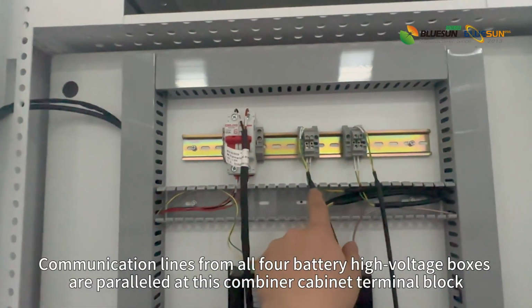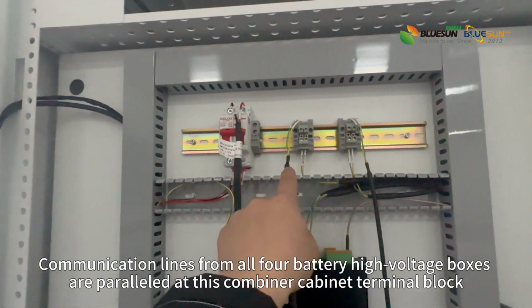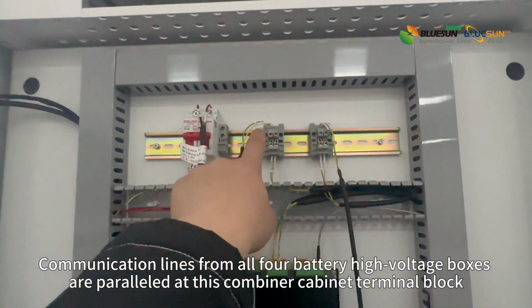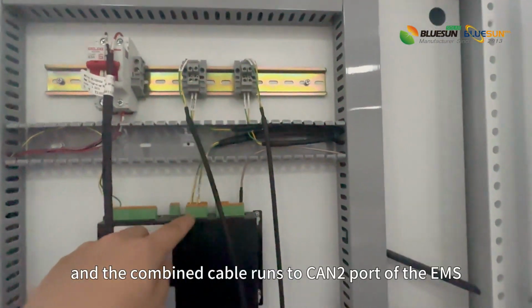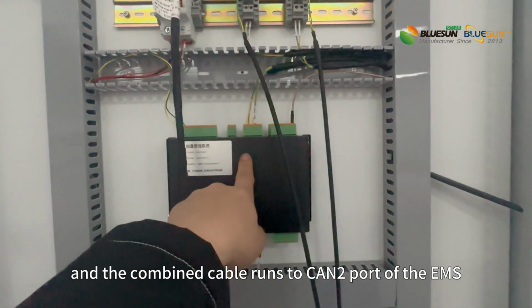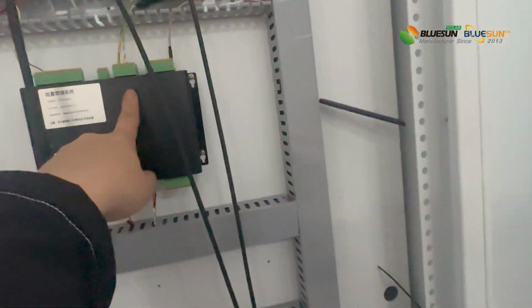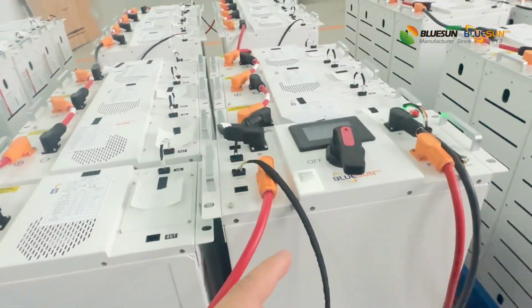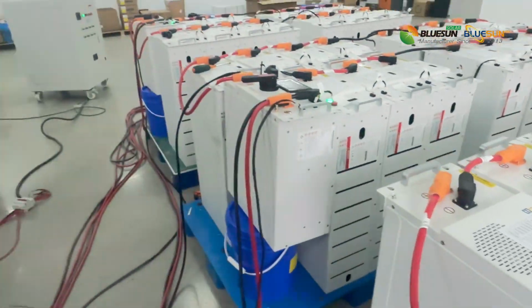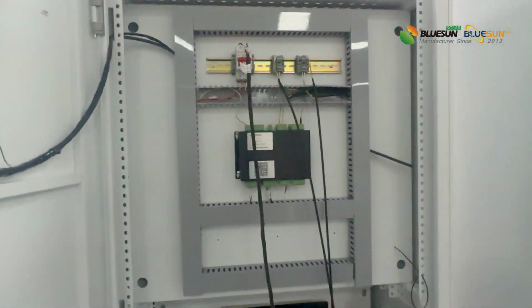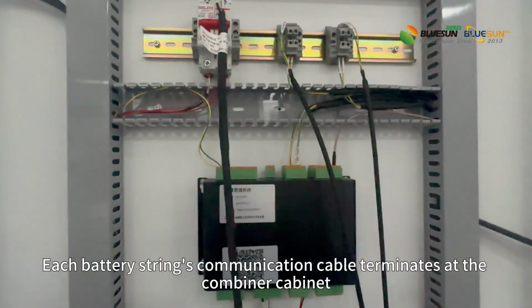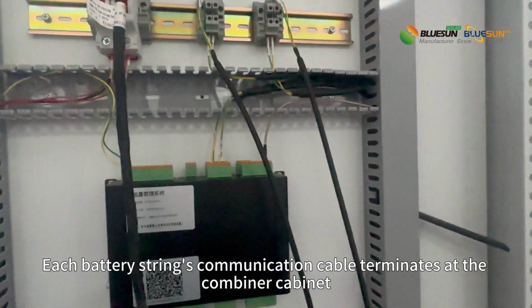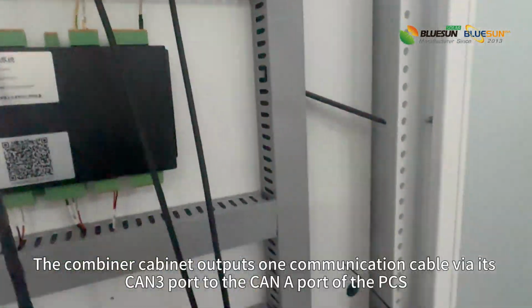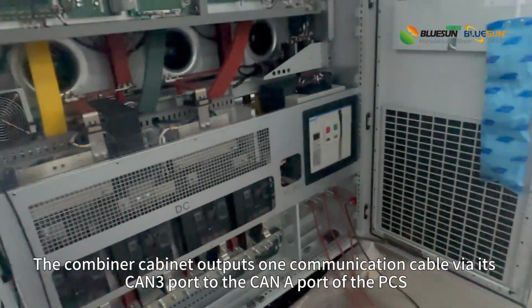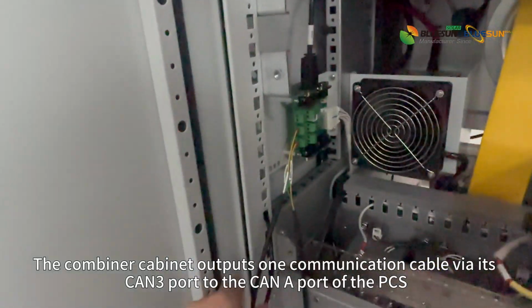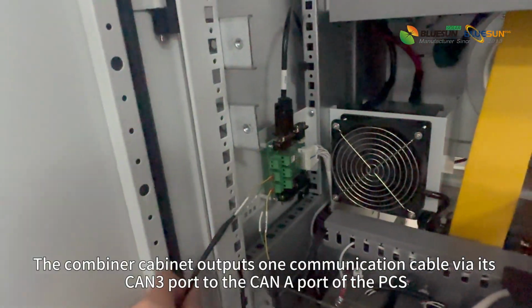Communication lines from all 4 battery high-voltage boxes are paralleled at this combiner cabinet terminal block, and a combined cable runs to the CAN 2 port of the EMS. Each battery string's communication cable terminates at the combiner cabinet. The combiner cabinet outputs 1 communication cable via its CAN 3 port to the CAN A port of the PCS.